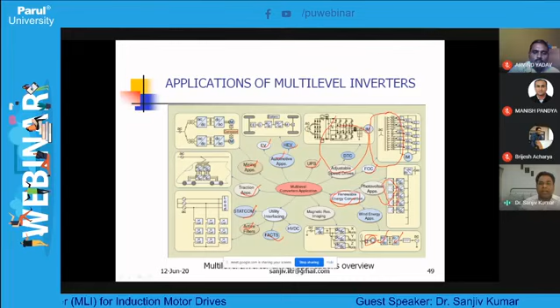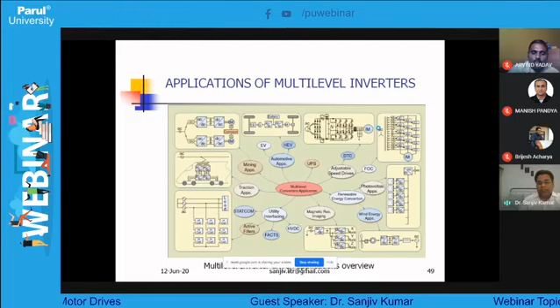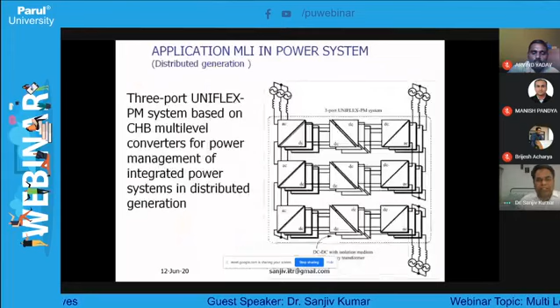Here you can see multipulse rectifiers are used. It could be a 24-pulse rectifier, where we generate plus 22.5, plus 7.5, minus 7.5, minus 22.5 phase-shifted rectifier, meaning in the primary there is one star or delta connection, and in the secondary there are 4 secondary windings which are phase shifted by these angles. So input current is also improved, and at the same time, since you are using the multi-level inverter, output is also improved. That is called a multi-pulse, multi-level inverter based induction motor drive. That is another area where you can apply this, and these are all the details of this application. All these are the applications.